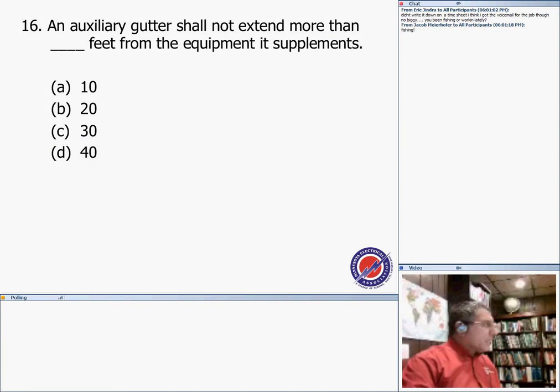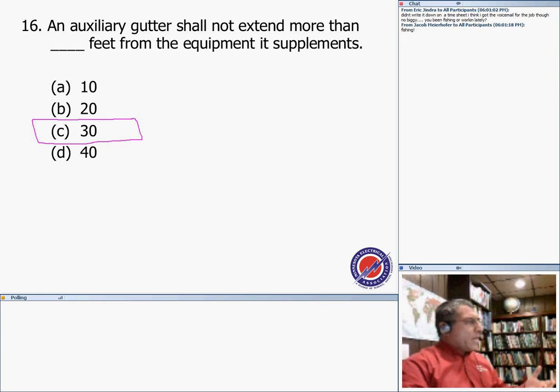Number 16. The auxiliary gutter shall not extend more than how many feet? And that's what makes an auxiliary gutter, guys, not a wireway or raceway. It has a limitation of up to 30 feet. It's an extension of the equipment. So 30 feet to extend a piece of equipment. I don't know about you, Joe, my friend. That's a heck of a piece of equipment to extend 30 feet.